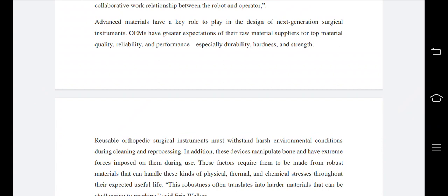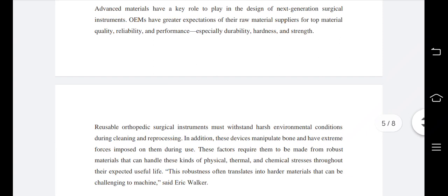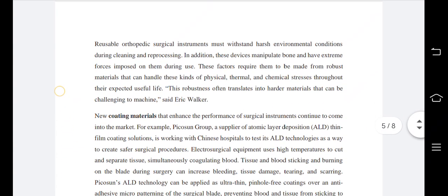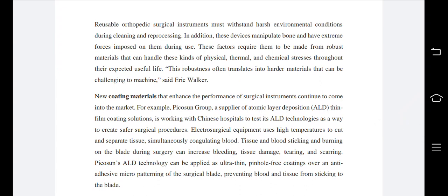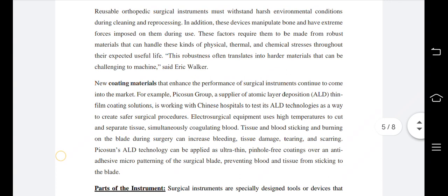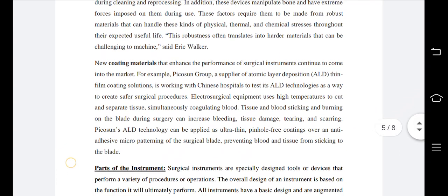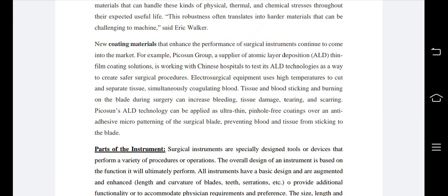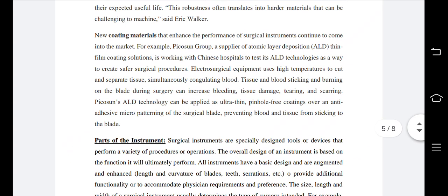Advanced materials have a key role to play in the design of next generation surgical instruments. Original equipment manufacturers have greater expectations of their raw material suppliers for top material quality, reliability and performance, especially durability, hardness and strength. Reusable orthopedic surgical instruments must withstand harsh environmental conditions during cleaning and reprocessing. In addition, these devices manipulate bone and have extreme forces imposed on them during use. These factors require them to be made from robust materials that can handle these kinds of physical, thermal, and chemical stress throughout their expected useful life. This robustness often translates into harder materials that can be challenging to machine, said Eric Walker.